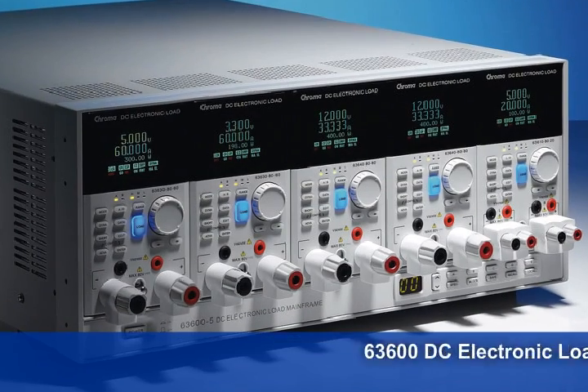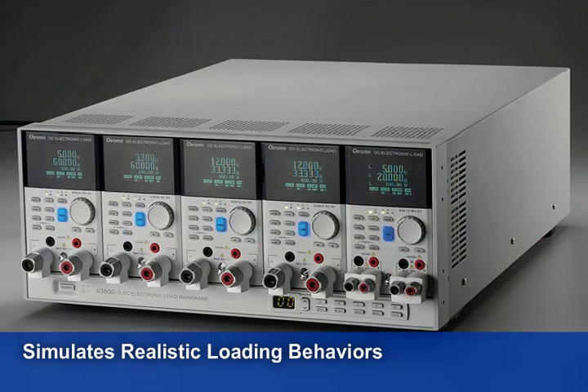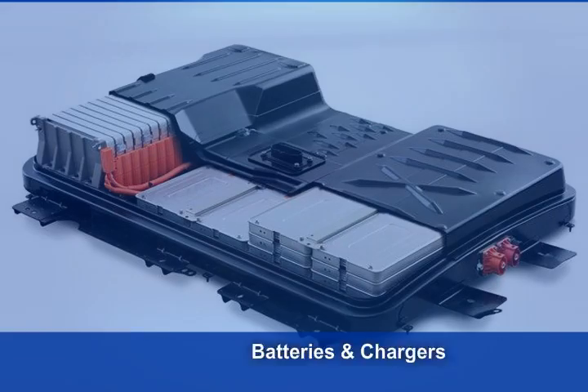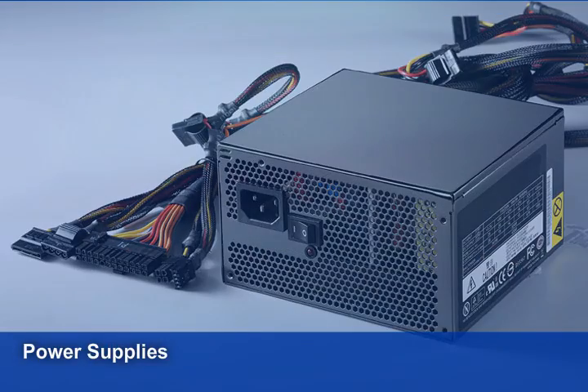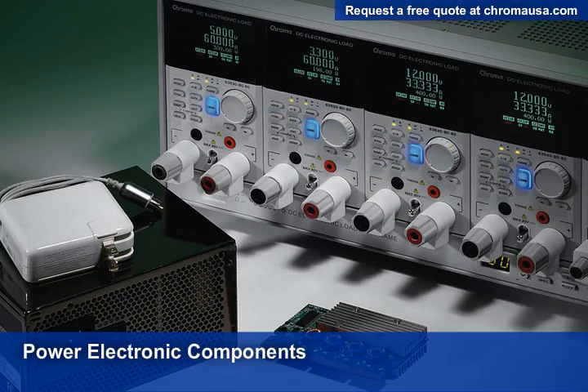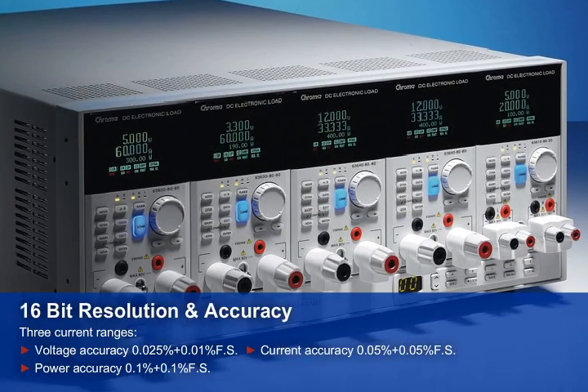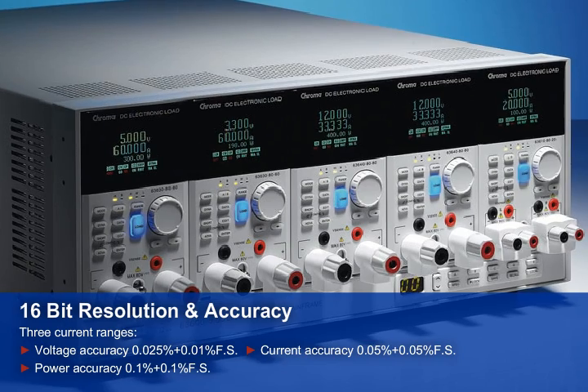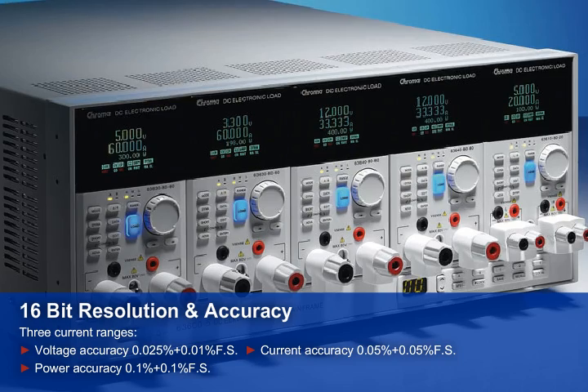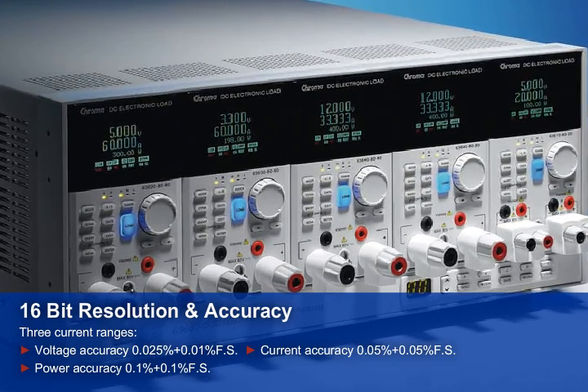Chroma 63600 DC electronic loads use exclusive state-of-the-art technologies and operation modes to simulate realistic loading behaviors for a wide range of applications, including batteries and chargers, multi-output power supplies and converters, fuel cells, solar panels, and other power electronic components. Real-time measurements are integrated into each load module using a 16-bit measurement circuit with three operating current ranges for unbelievable voltage, current, and power measurement accuracy throughout the entire range of operation.